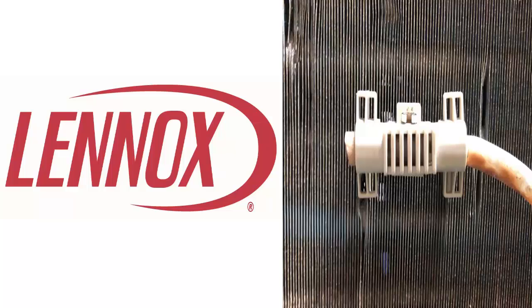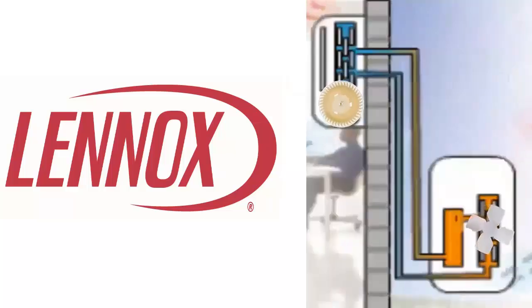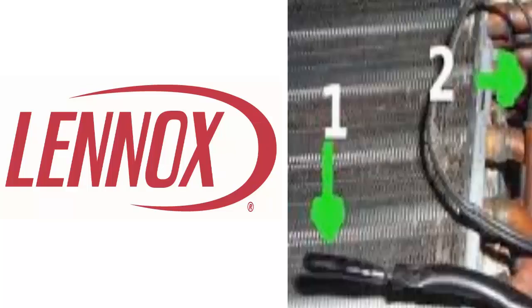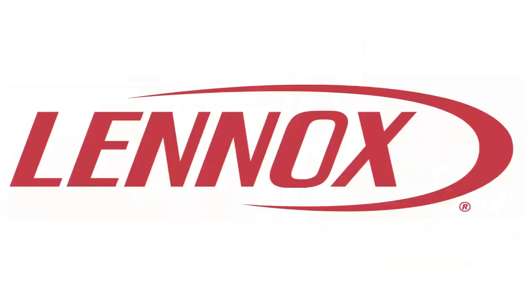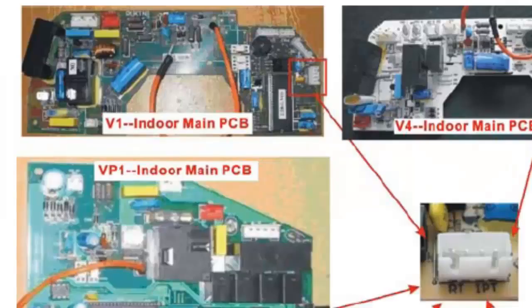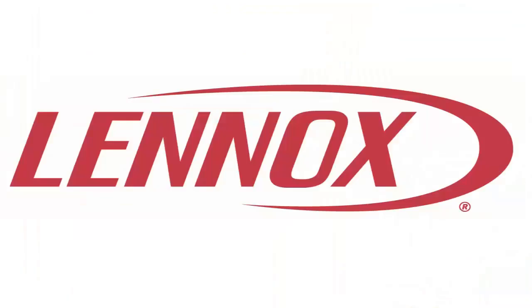3. Check the sensor's position. Ensure that the sensor is properly placed and secure in its position. 4. Verify that the sensor's connections to the electronic board are secure and that the cables are not damaged. 5. Disconnect and reconnect the sensor. Clean the connections if necessary.